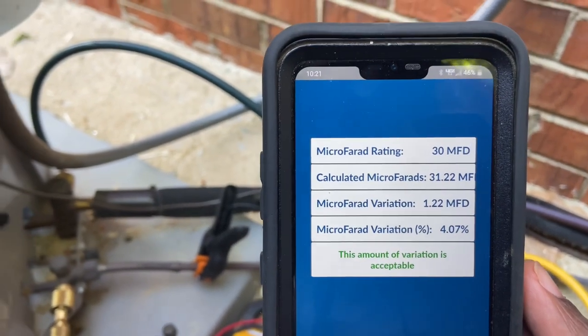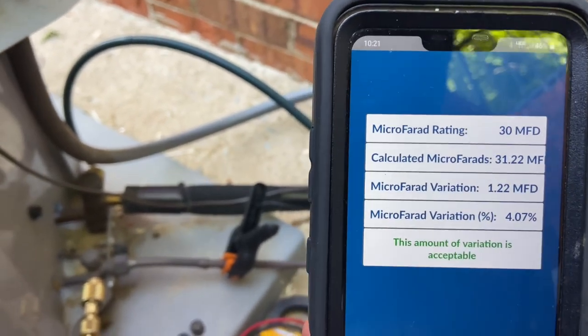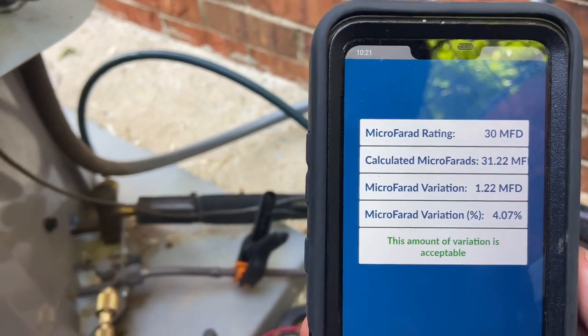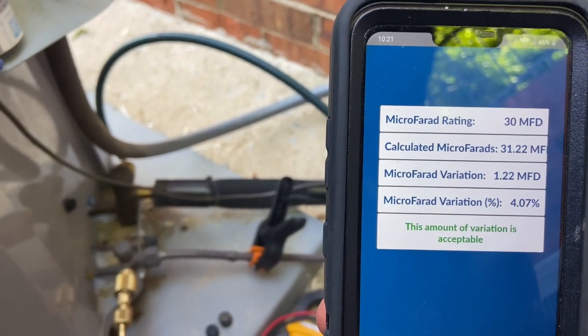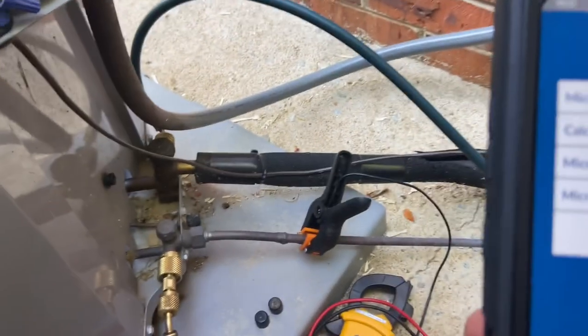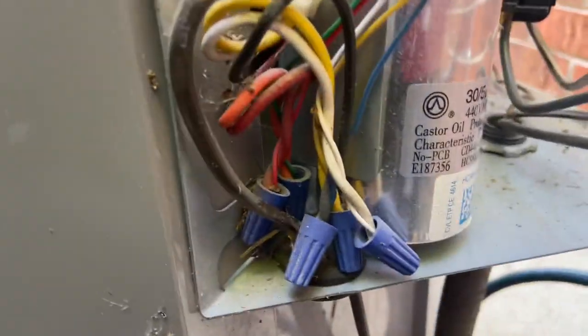That gives you a full reading. It shows the rated microfarads, which was 30, and the calculated microfarads — which came out to 31.22. The variation is 1.22 microfarads over, which isn't bad. The variation percentage is 4.07%, which is pretty good.